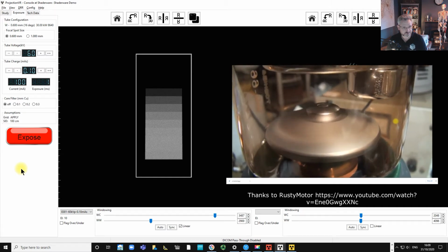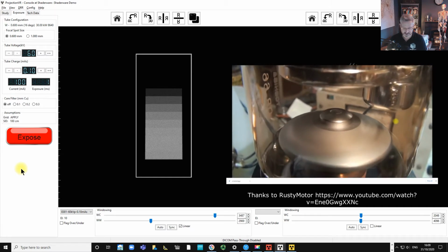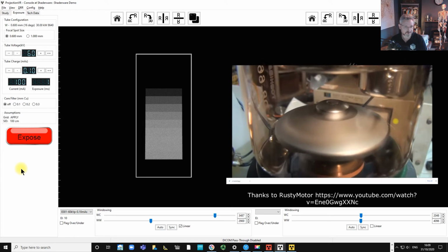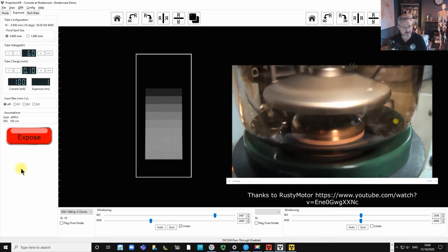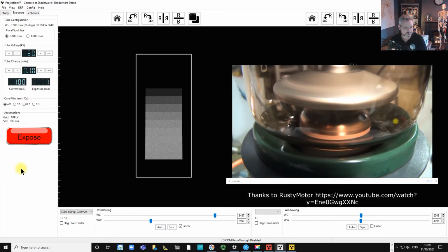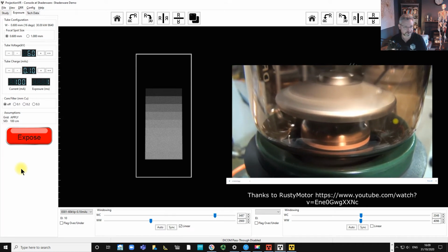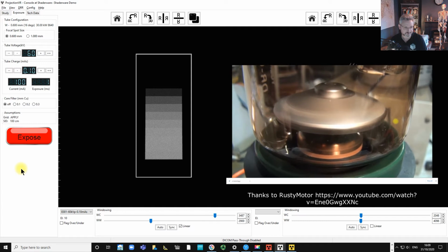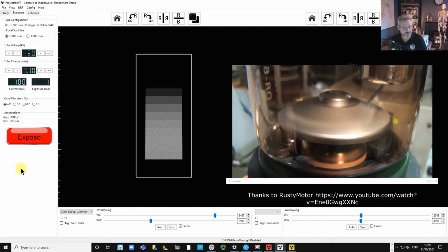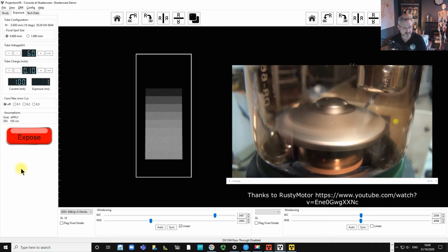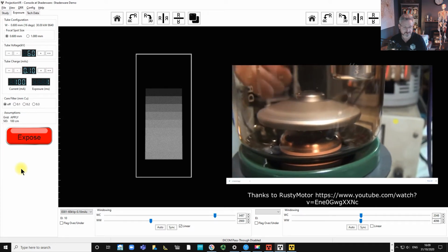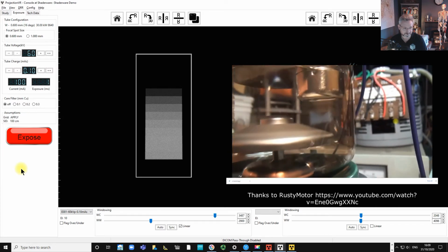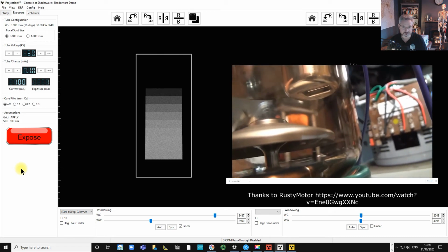its fastest revolutions. So the X-ray tube anode is what's called a moving anode, a rotating anode, and that anode will be spun up using an electric motor, an induction motor called a stator. It'll be spun up to about 9,000 revs per minute. So a lot of revolutions per minute, 9,000. So it's going very quickly. And you hear the noise of it spinning up.